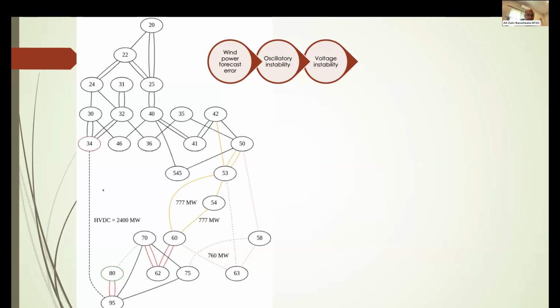And this brings us to our HVDC line. As for the HVDC line at bus 34, you see on the left, this is a receiving end of the HVDC line. As most of you know, AC systems are managed through frequency control. Well, an HVDC line is managed through voltage control. Specifically at the receiving end, you need a very stiff voltage. The voltage should not move from its nominal value, in this case 500 kV at the AC side of the DC converter. Except with the oscillating power, the voltage is moving between 550 and 450. This is obviously massive and cannot be sustained.